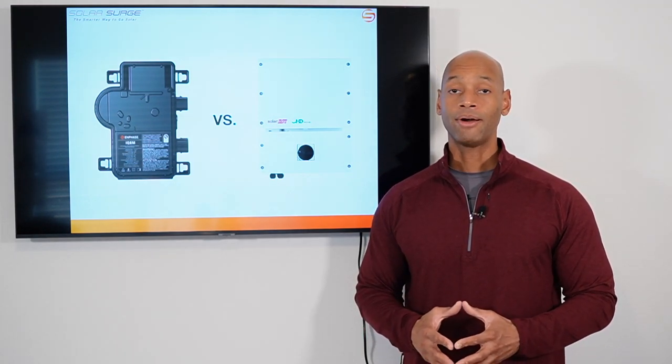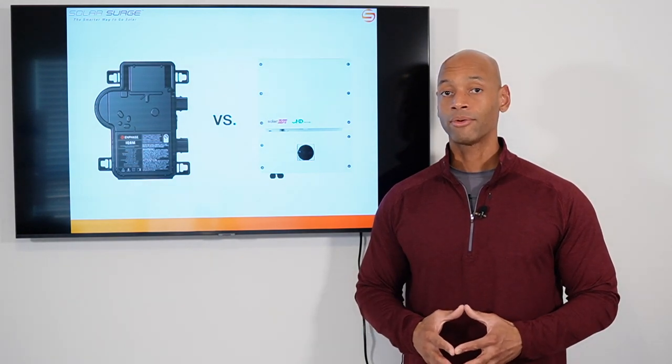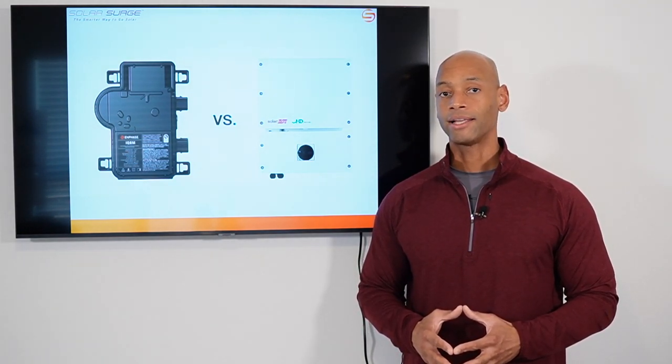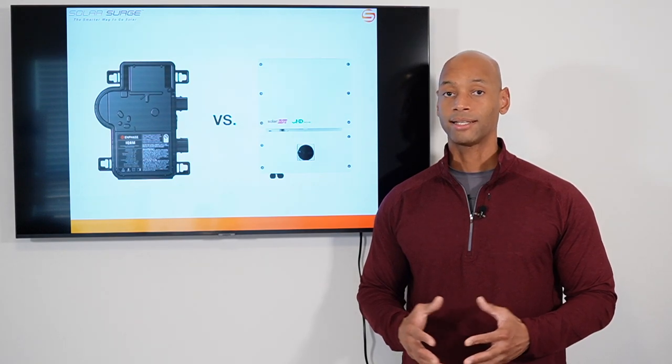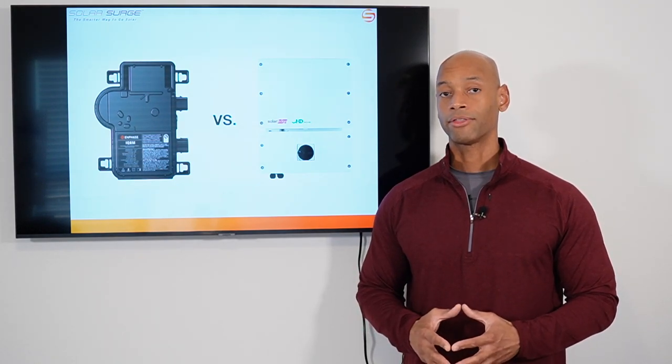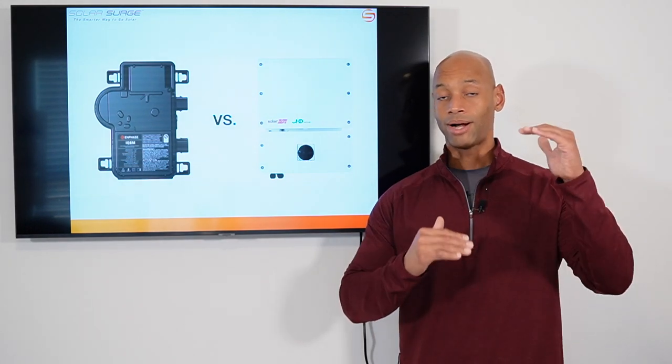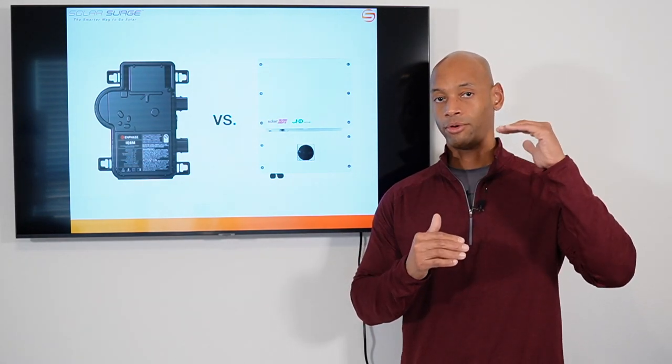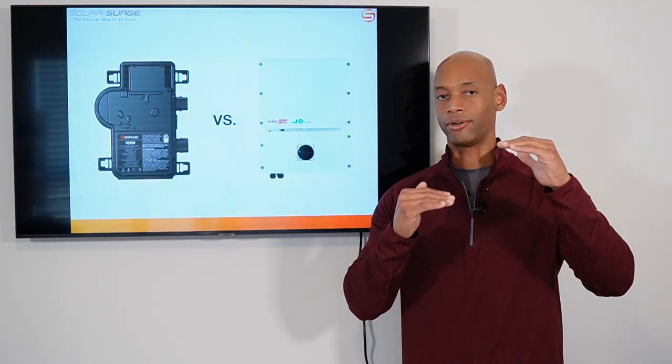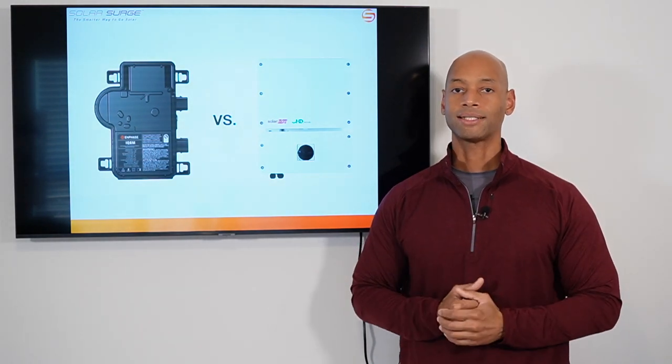So as of this recording, one of our most popular solar panels for residential installations is the Aptos 440 watt panel. However, the most popular microinverter that we're pairing with that is the Enphase IQ8A, which still has a continuous power rating of only 349 or 350 watts. So there is a 90 watt difference there in terms of what the panel can do at max versus what the microinverter can sustain at max output.